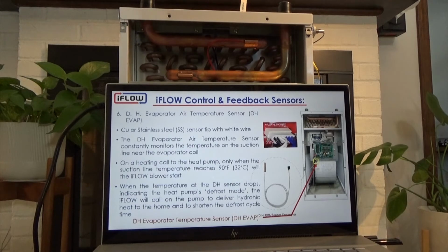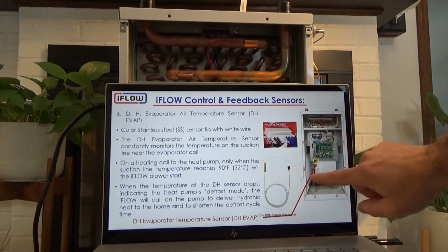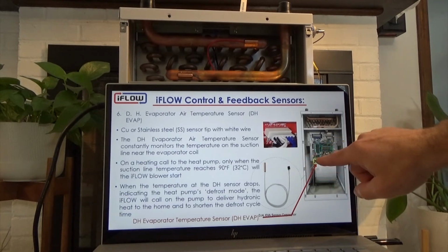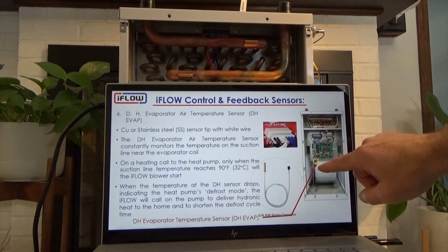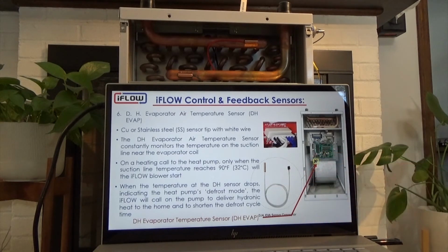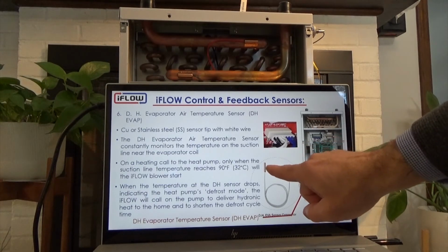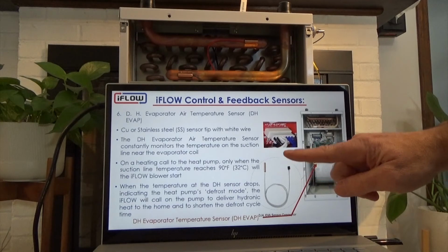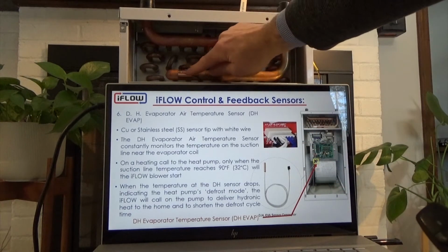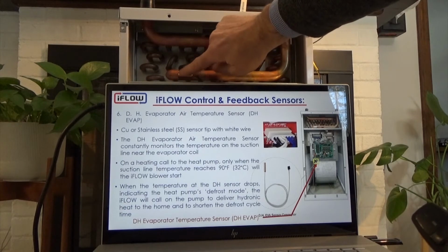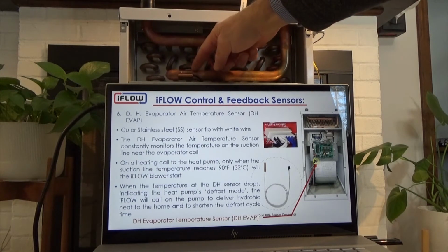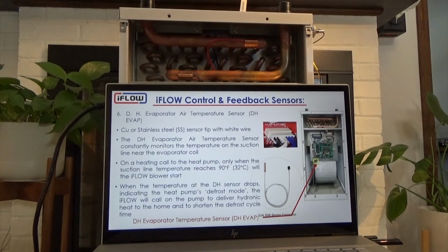Okay, then we have a DH evaporator temperature sensor. This is looking at the temperature. It will connect on the unit with this black harness just above or just below the lower left corner of the board, kind of above the blower. So that's where it's located inside the unit. And then it's going to wire and connect to the suction line just close to the evaporator, and measure the temperature on the suction line. You'll probably use some tape or some sort of harness and strap it on to your suction line outside, in a similar way to how we are doing with those sensors.